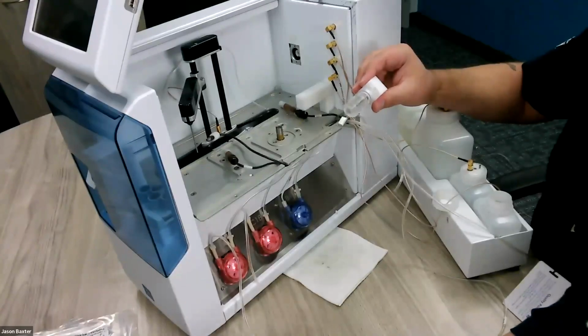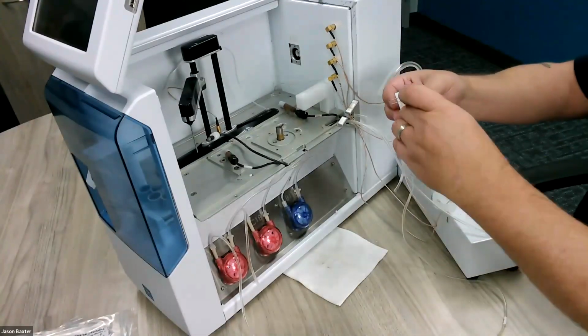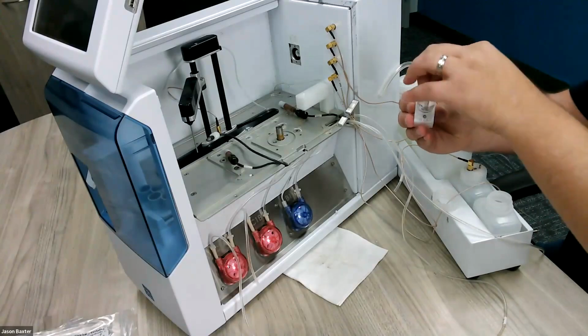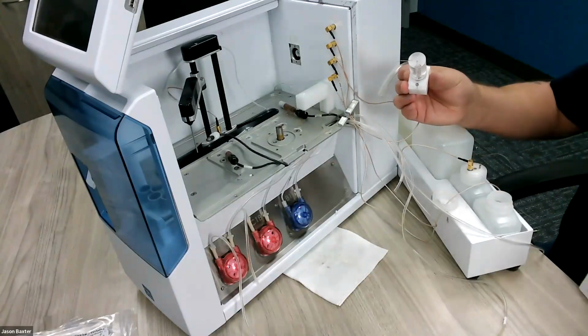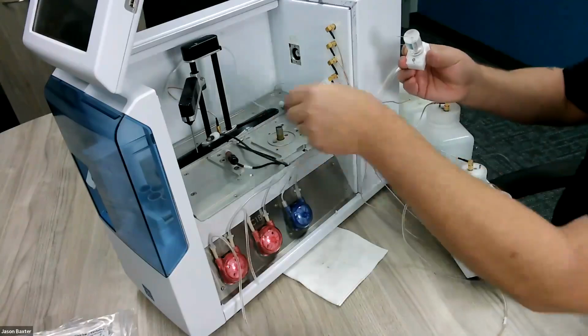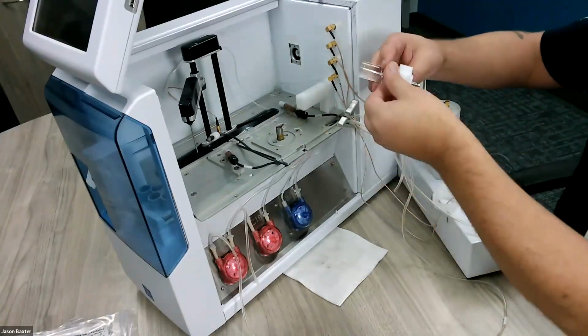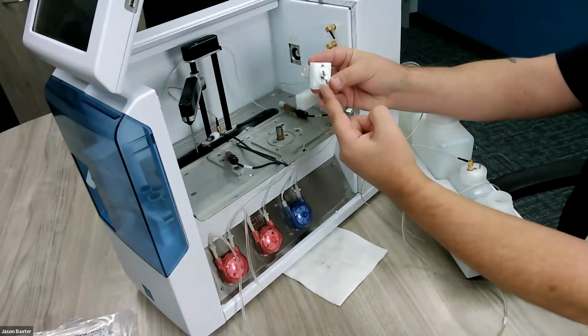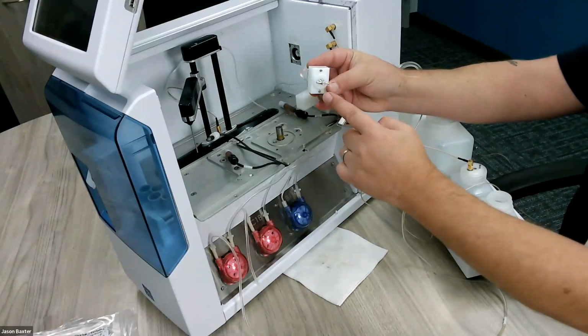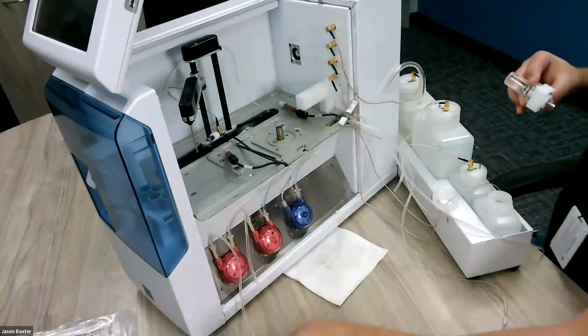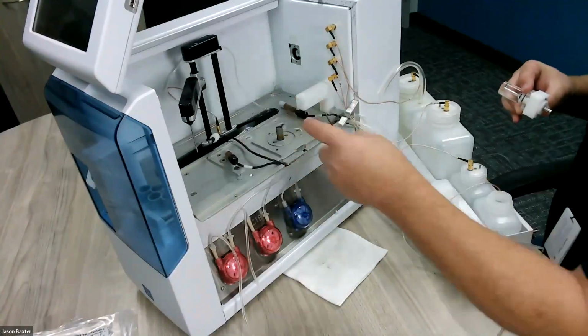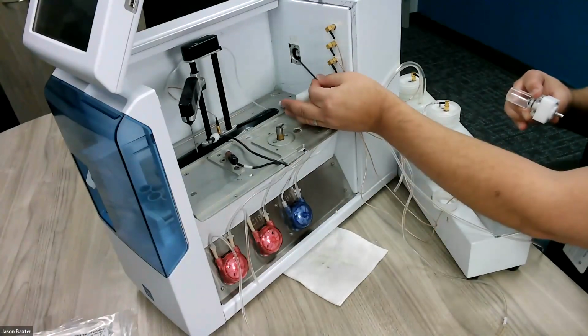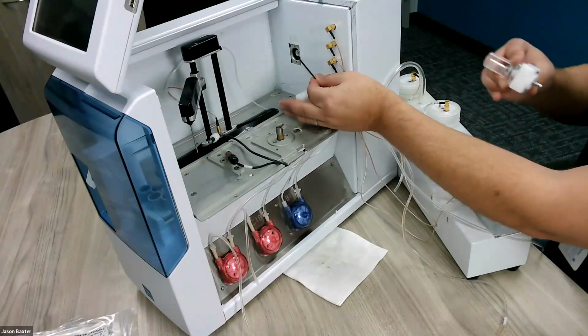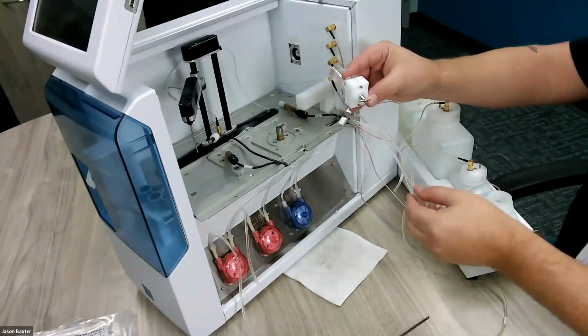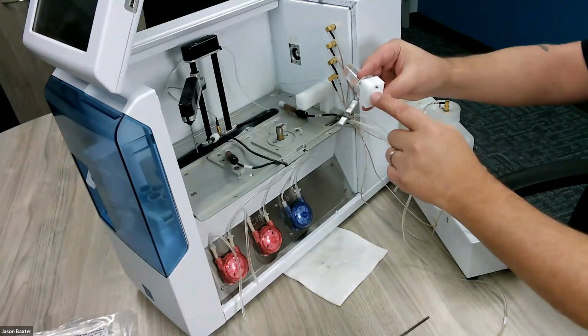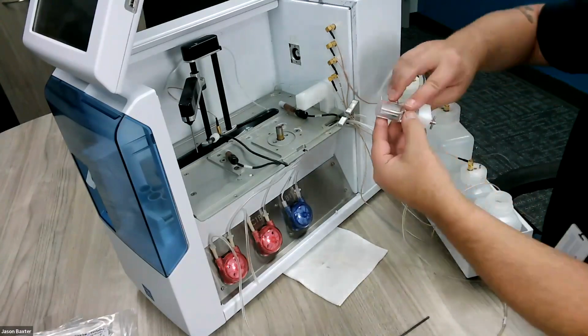Find your 2 bolts for your zipper pump housing. I will usually put these into place just so I have one less thing to chase around. I make sure I know where my 3/32 Allen wrench is. At reassembly, you'll notice the backside of the zipper pump has this, what I call the T-bar on it. When you look back inside of the chassis, where did it go? There it is. When you look back inside of the chassis, you'll notice the driver also has a cutout that lines up with the T-bar. So just take a moment, and if it's not lined up, just line it up by hand, however you need to do it.